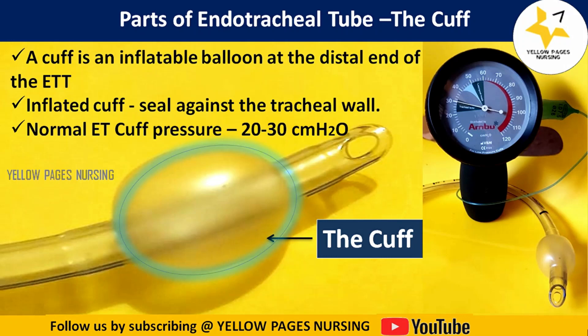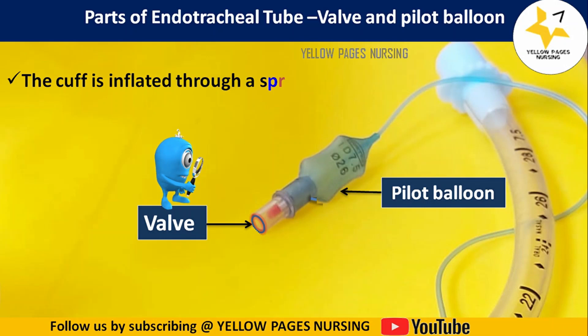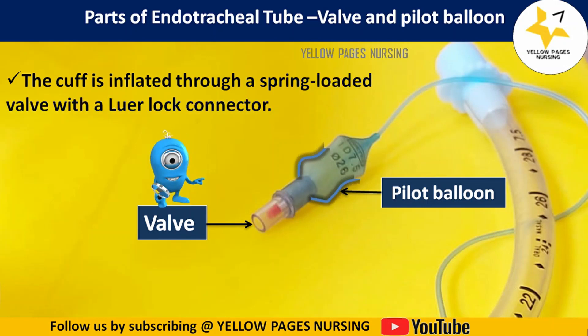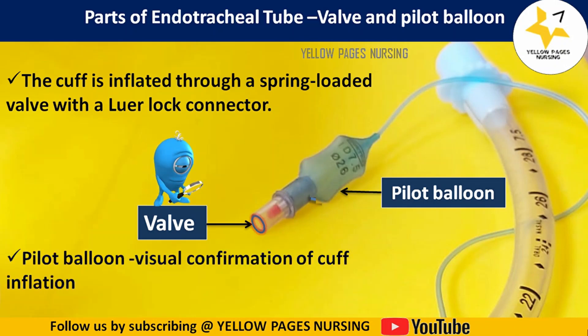There are two types of cuffs: high volume low pressure cuffs and low volume high pressure cuffs. The cuff is inflated through a spring-loaded valve with a luer lock connector. Just above this is a pilot balloon which visually confirms the cuff inflation, but ideally cuff pressure should be checked by a cuff pressure manometer.